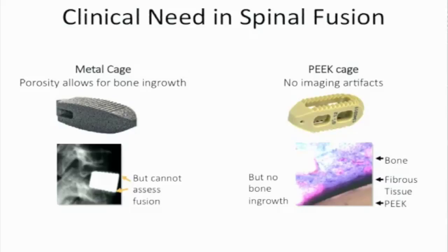And there's another argument: its stiffness is closer to bone. So the argument is you have a better stiffness relative to bone. The problem is PEEK doesn't like to stick to bone. So this cage is probably 30 or 40% of the area that you're putting in there, and the rest is bone graft. So you have a reasonable fraction of the area that's not participating in the fusion, and it makes it a risky endeavor in terms of the fusion. So this has been a dilemma.